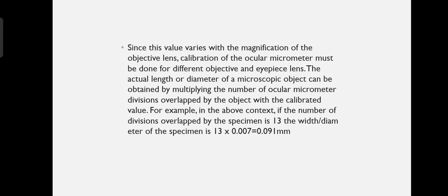Therefore, calibration is the process of determination of the magnitude of one division of the ocular micrometer at a particular magnification with the help of a stage micrometer. Here, the value of an ocular micrometer division is calibrated as 0.007 mm. Since this value varies with the magnification of the objective lens, calibration of the ocular micrometer must be done for different objective and eyepiece lenses. The actual length or diameter of a microscopic object can be obtained by multiplying the number of ocular micrometer divisions overlapped by the object with the calibrated value. For example, in the above context, if the number of divisions overlapped by the specimen is 13, the width of the specimen is 13 × 0.007, which is equal to 0.091 mm.